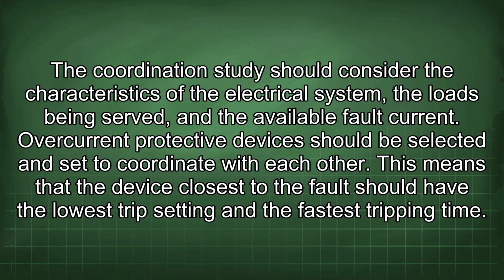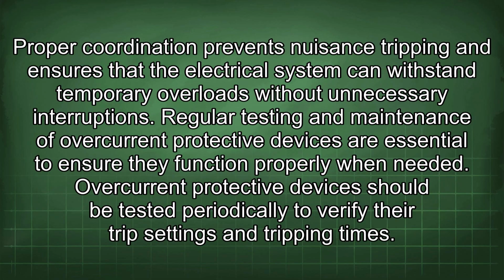Overcurrent protective devices should be selected and set to coordinate with each other. This means that the device closest to the fault should have the lowest trip setting and the fastest tripping time. Proper coordination prevents nuisance tripping and ensures that the electrical system can withstand temporary overloads without unnecessary interruptions.